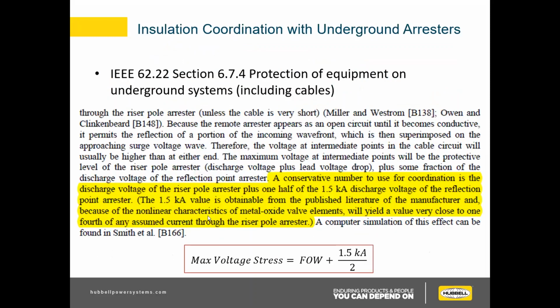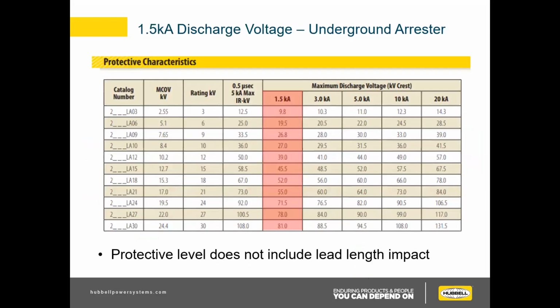This is another excerpt from the 62.22 standard about when you include underground arrestors. Pretty much the same thing here. A conservative number to use for coordination is the discharge voltage of the riser pole arrestor plus 1/2 of the 1.5 kA discharge voltage of the reflection point arrestor. That would be an elbow arrestor in the green box. This is a good rule of thumb. It says here values will change depending on manufacturer, of course, but this is a very close estimate that you can use if you don't have a manufacturing or a sales drawing in hand. This will all make a little more sense in a second.